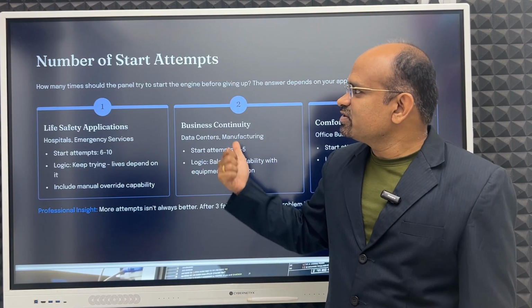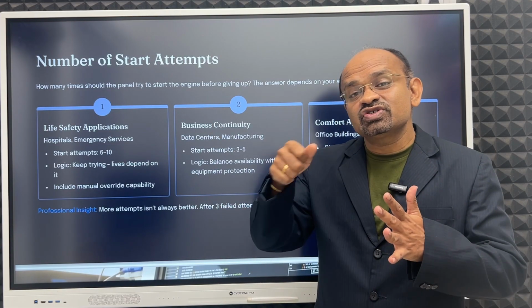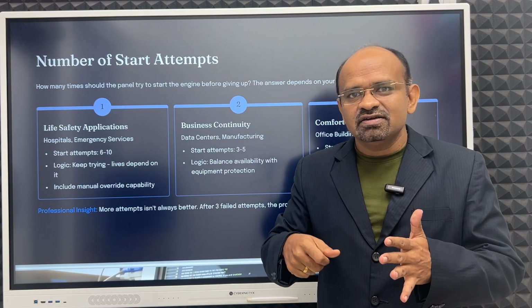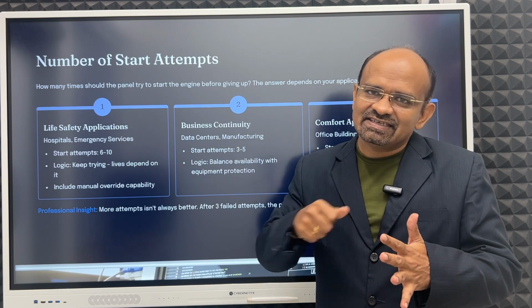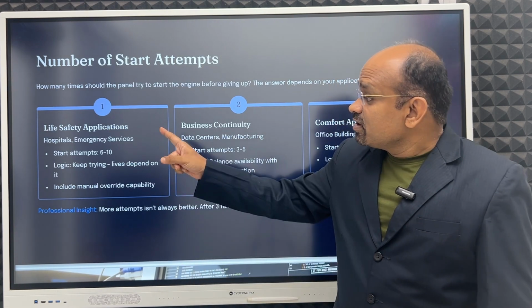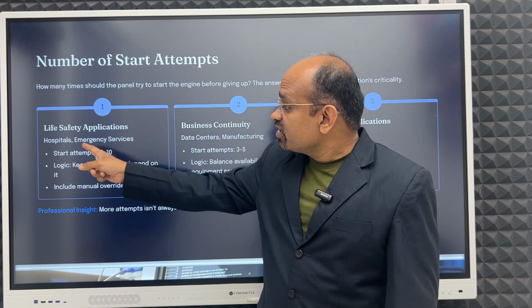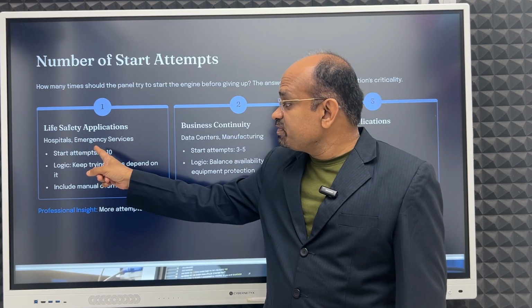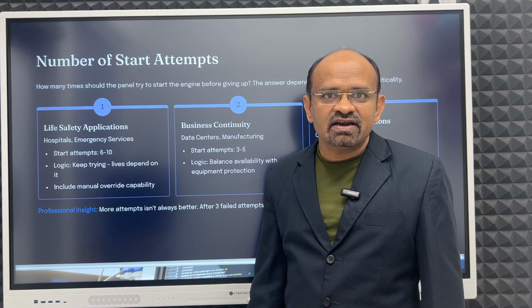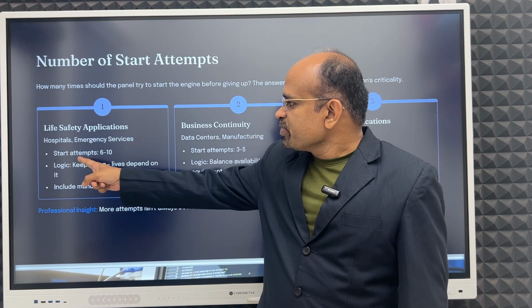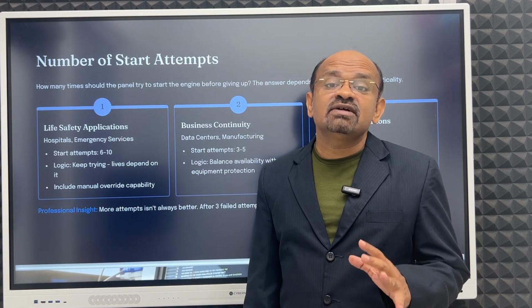There is a setting for how many times you should crank. 1, not starting. 2, not starting. 3, not starting, give up. Then, depending on load and life safety applications like hospitals or emergency and fire related services, 6 to 10 start attempts can be done.